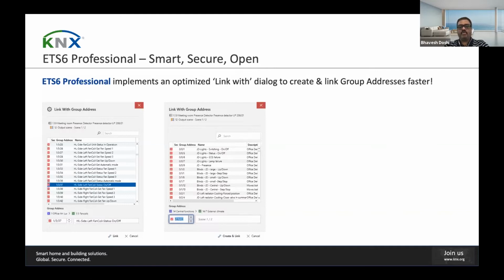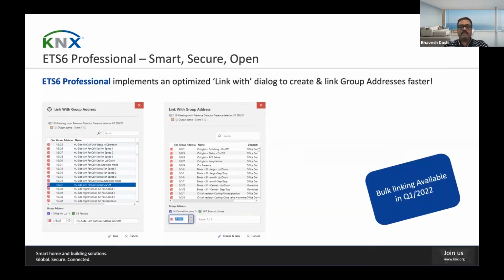Furthermore, multiple linking is also supported, which means multiple group objects and channels can be selected on the device as a source for the linking, where the target can be functions of group addresses for each object. So in ETS6, we support the bulk linking of group objects with group addresses. As a note, the bulk linking will be available within the first quarter of 2022.